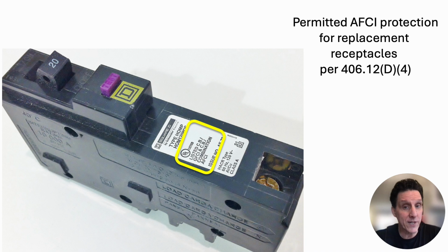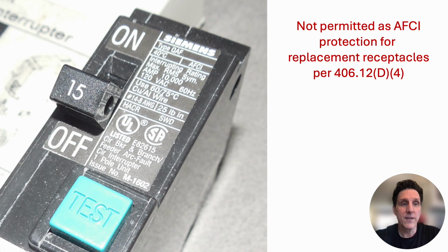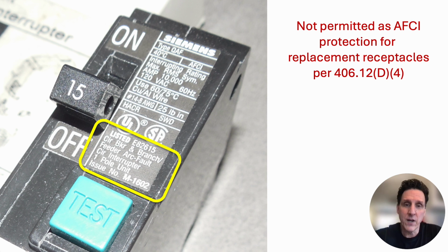I'm going to show you another circuit breaker. Now, this is an AFCI breaker, but you cannot use this type to provide AFCI protection for replacement receptacles, and that's because this is not a combination type of AFCI. If you look where I have the yellow highlight there, this is only a branch circuit/feeder AFCI.